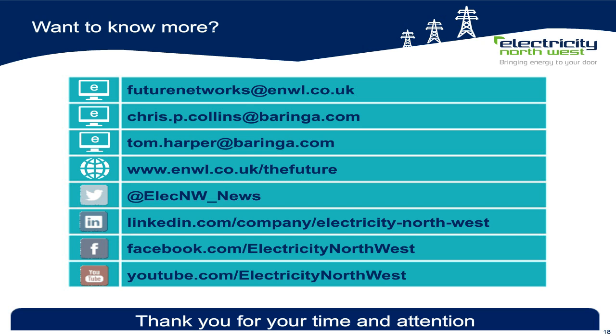If I could just add to that, we can carry out peak demand reduction at individual sites, but it is an individual site that you're probably going to require that. So in effect, it's going to have very little issue or response to the TSO or what they need to do. So the actual load level will be very low. And the other thing to say is that remember that CLASS is a portfolio response. You've got multiple substations which collectively provide the service. So if there is an issue on any individual substation that happens to be near its local peak, there's no reason that CLASS can't take that out and put another substation in its place. It's a fairly responsive service in that way.